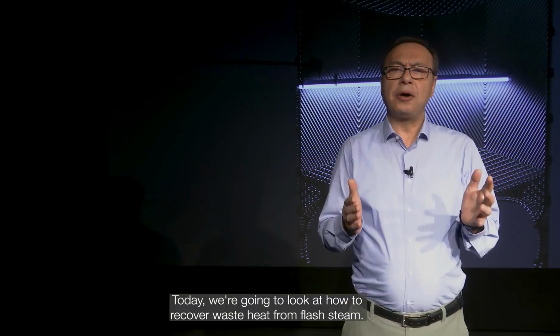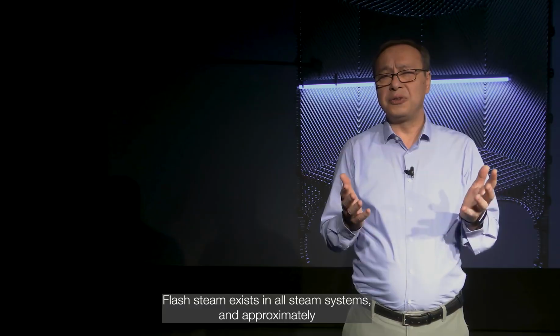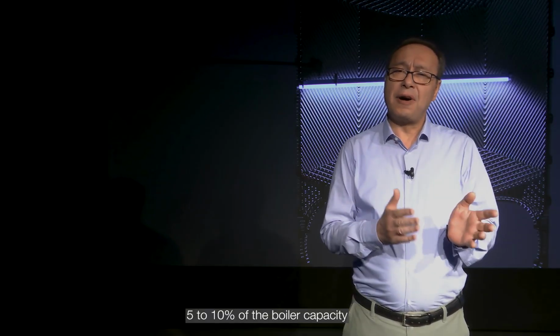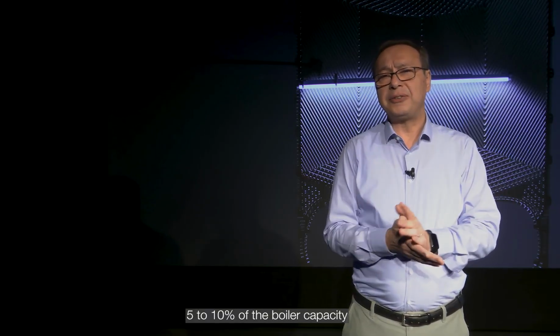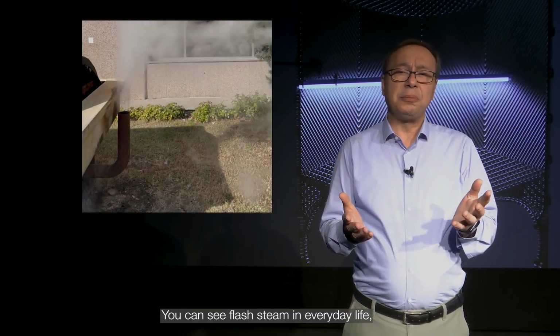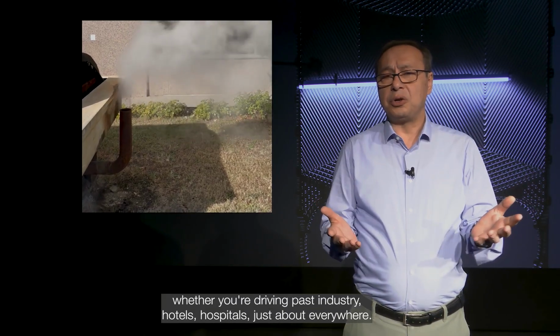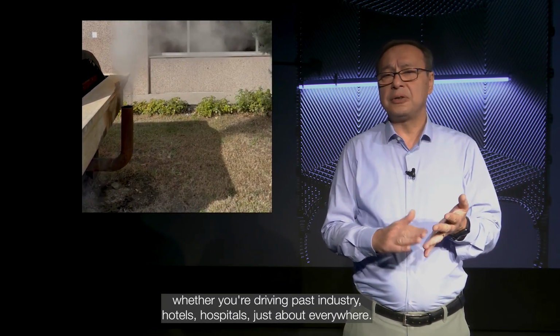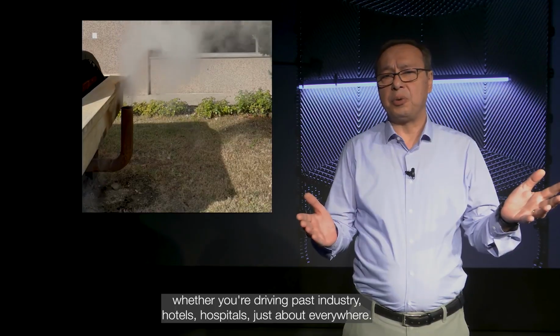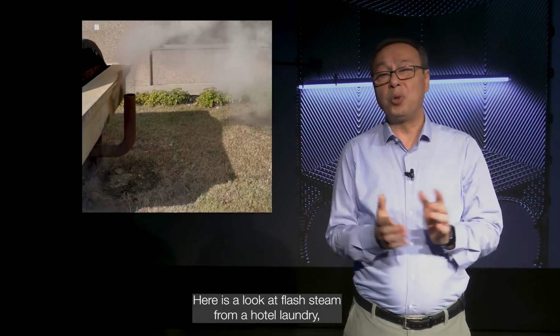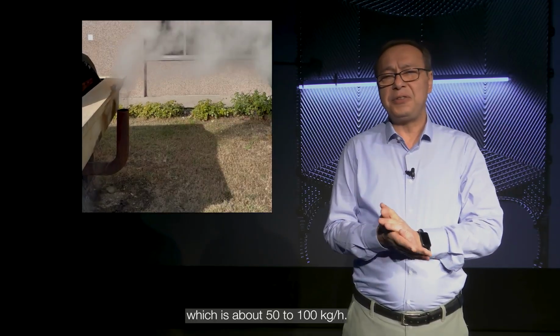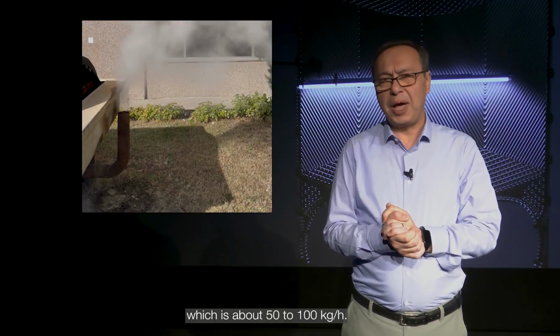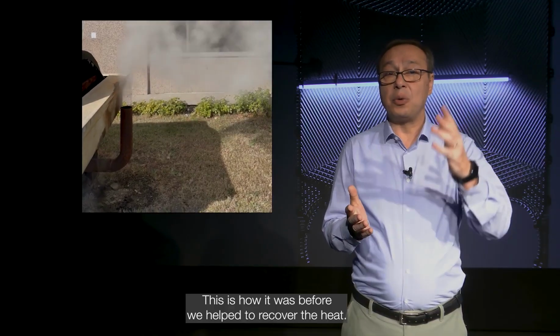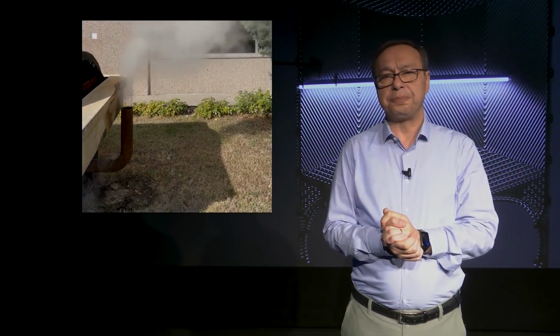Today we're going to look at how to recover waste heat from flash steam. Flash steam exists in all steam systems, and approximately 5 to 10% of the boiler capacity is released as flash steam. You can see flash steam in everyday life, whether you're driving past industry, hotels, hospitals, just about everywhere. Here is a look at flash steam from a hotel laundry, which is about 50 to 100 kilograms per hour. And this is how it was before we helped to recover the heat.